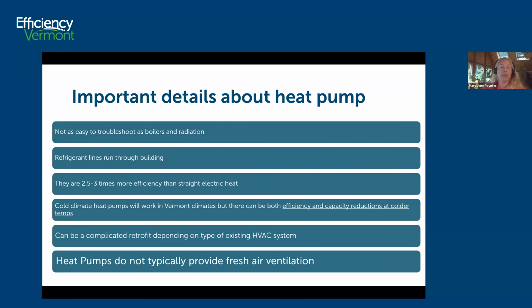And then the third thing is heat pumps do not typically provide fresh air ventilation. So if the system that is in the building right now is like a rooftop unit, those do bring in ventilation. You switch over to heat pumps, turn off your rooftop unit, you may be starving your space of ventilation air. So those things need to be thought of when designing.